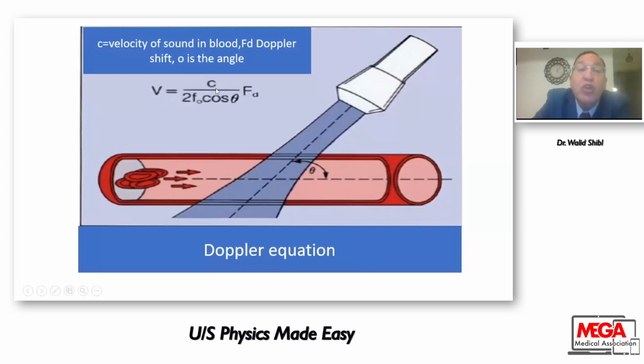is the velocity of the sound in the blood, a fixed number, 1540 meters per second, nothing to do, it is a fixed number, over 2 multiplied by the frequency of the probe, nothing to do, it's fixed. You cannot judge or control the frequency of the probe, it's a fixed number, multiplied by the cosine of the angle of insonation, multiplied by the frequency shift. So the velocity of the sound in the blood is fixed, the frequency of the probe is fixed, the frequency shift is fixed, nothing to do with, and we'll know what this frequency shift is.